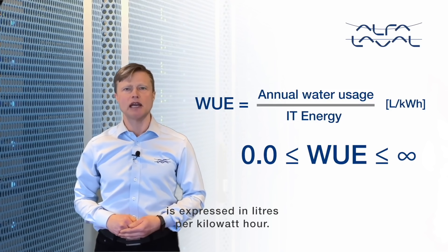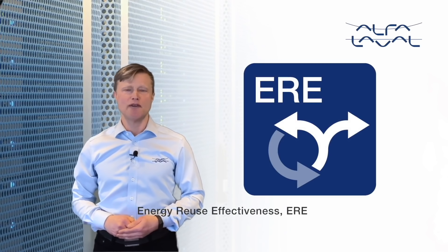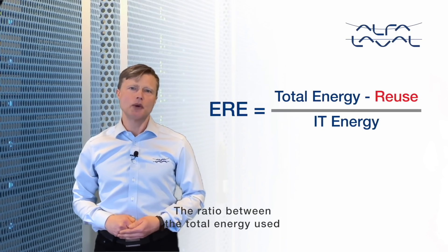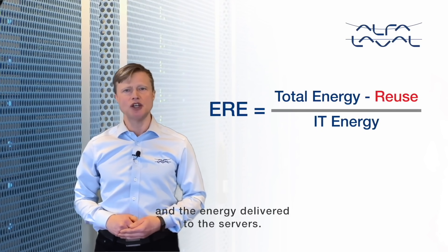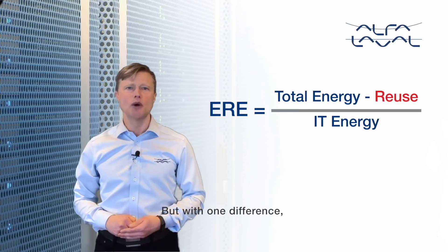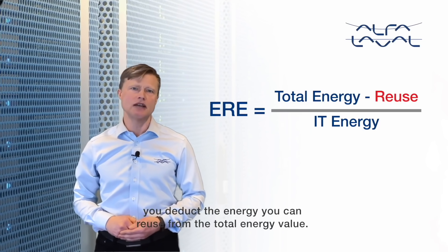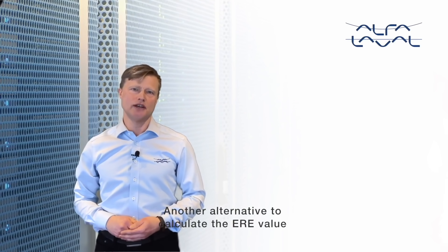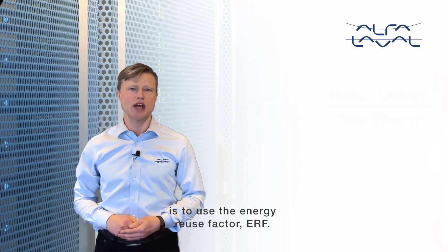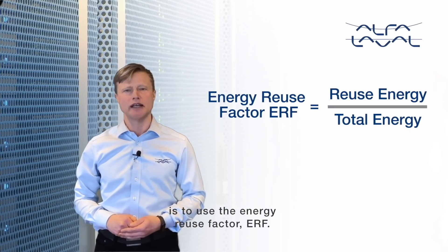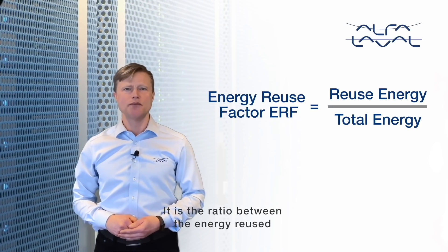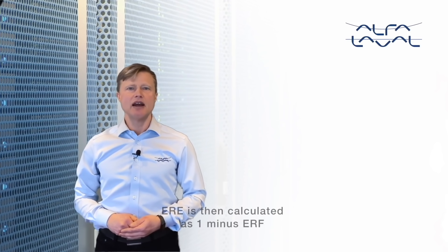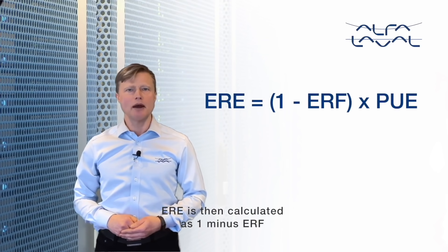Energy Reuse Effectiveness (ERE) is, like PUE, the ratio between the total energy used and the energy delivered to the servers — but with one difference: you deduct the energy you can reuse from the total energy value. An alternative way to calculate the ERE value is to use the Energy Reuse Factor (ERF), which is the ratio between the energy reused and the total energy. ERE is then calculated as one minus ERF, multiplied by the PUE value.